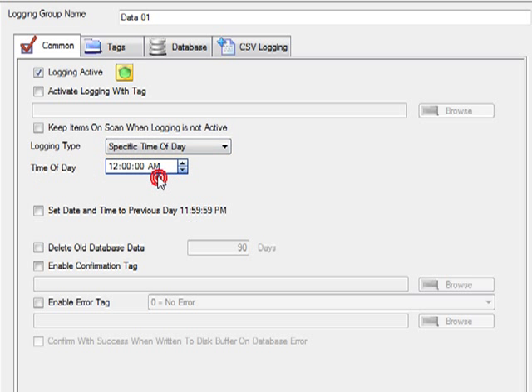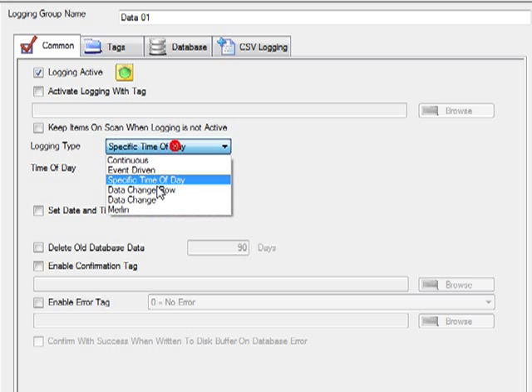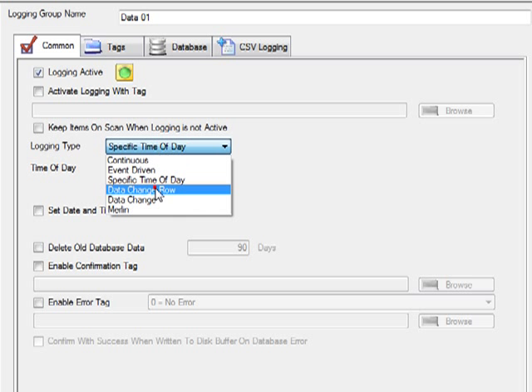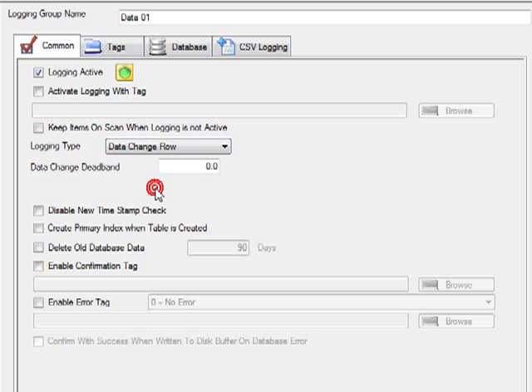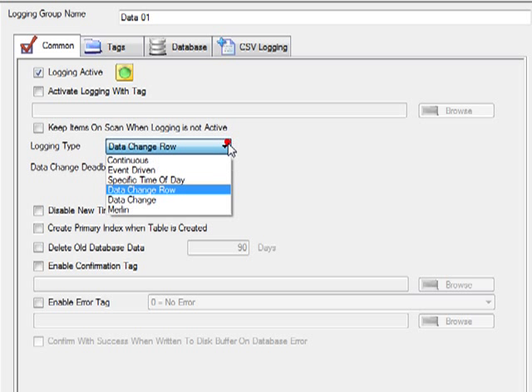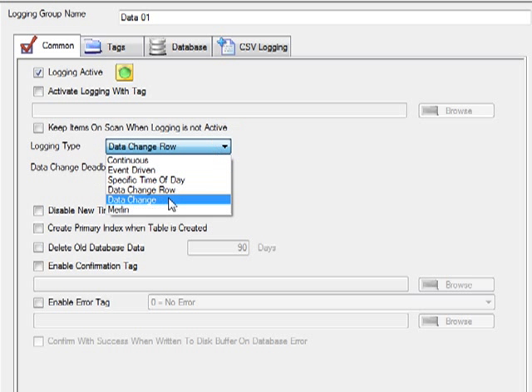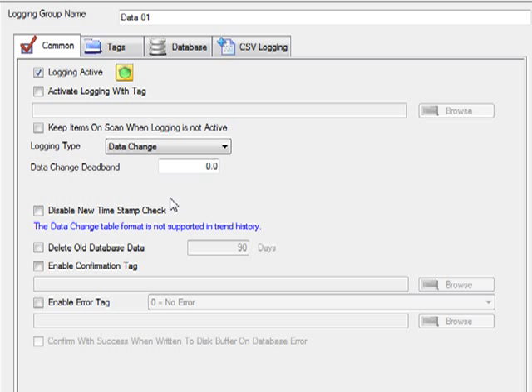We can log at a specific time of day. When we do this, for some systems you may want to roll back the date and time to the previous day. Also, you can use DataChangeRow. With this type, any one of the values changing causes a new record to be logged. There we have the deadband, which is the engineering units of the values that must change by in order for a new record to be taken. And we also have the DataChangeType.